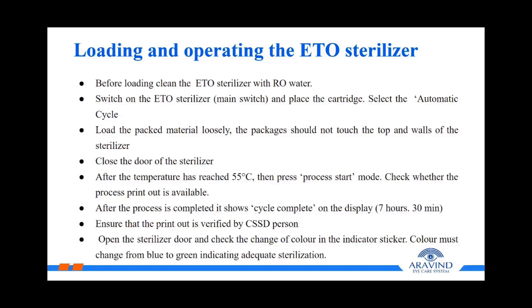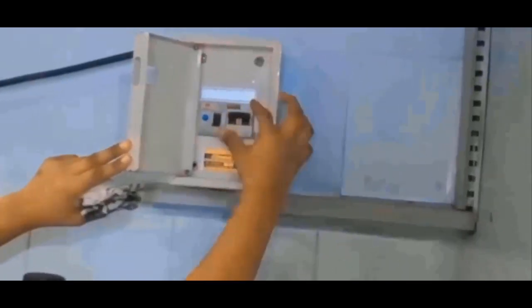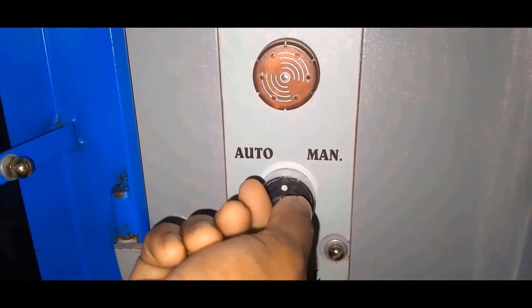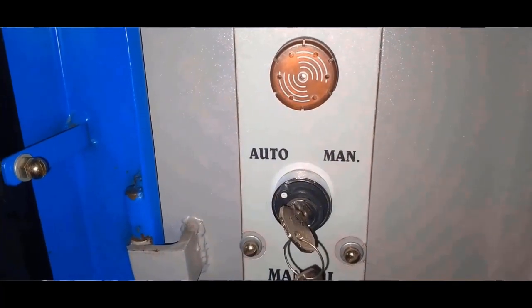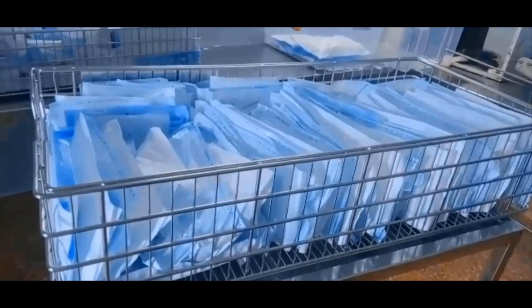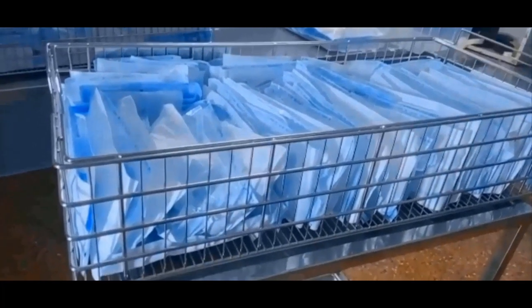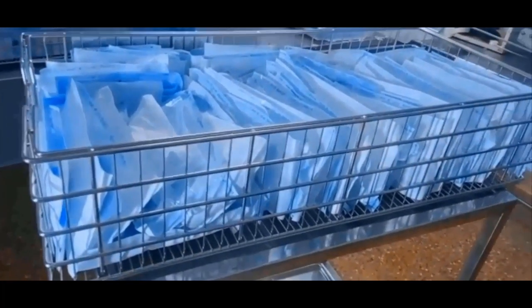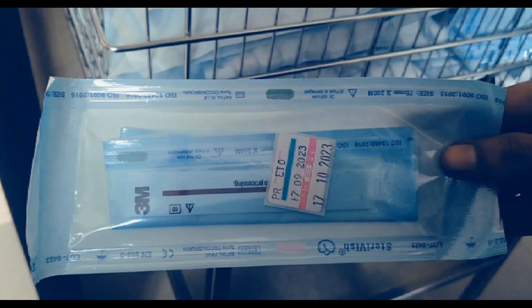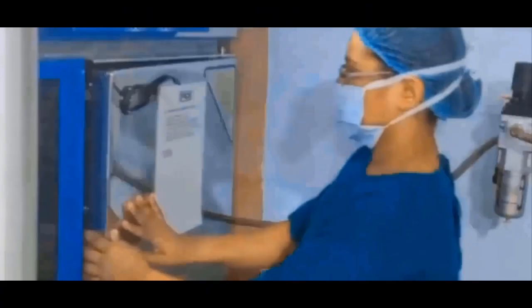Before loading, clean the ETO sterilizer with a dry cloth. Switch on the ETO sterilizer with the main switch and place the cartridge. Automatic cycle is selected. Load the packed material loosely and the packets should not touch the top and the walls of the sterilizer. A Class 4 indicator is double packed and placed in the center of the objects to be sterilized. Close the door of the sterilizer.